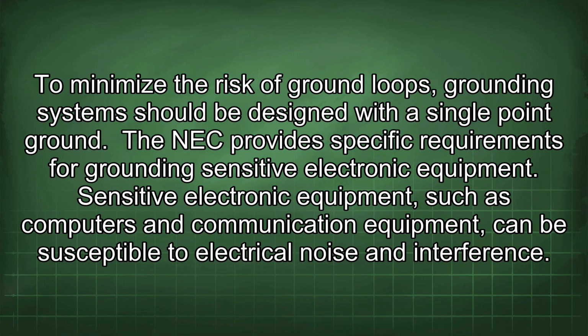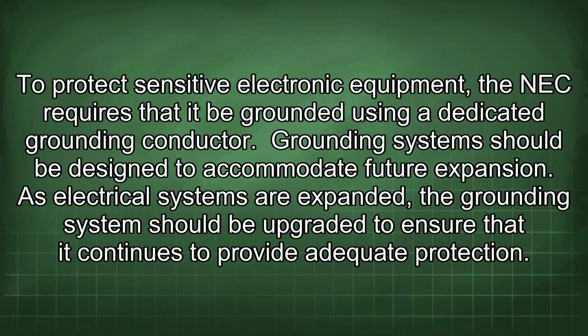The NEC provides specific requirements for grounding sensitive electronic equipment. Sensitive electronic equipment, such as computers and communication equipment, can be susceptible to electrical noise and interference. To protect sensitive electronic equipment, the NEC requires that it be grounded using a dedicated grounding conductor.